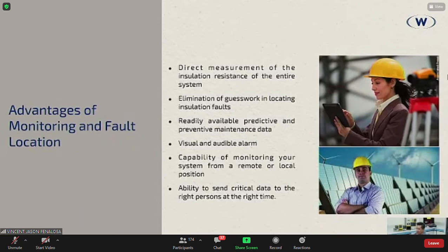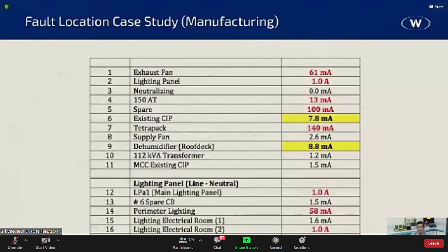Okay. Now, here's an actual snippet of a test result using a portable fault locator. If you look here, which one would concern you a lot? I'll give you a hint. It's right there. 1 amp on the lighting panel. So we followed that downstream. We found it. Downstream further, found it again. However, we were not able to go down further because we were not allowed to. But at least we know for a fact where it is. Lighting electrical room 2. So there.